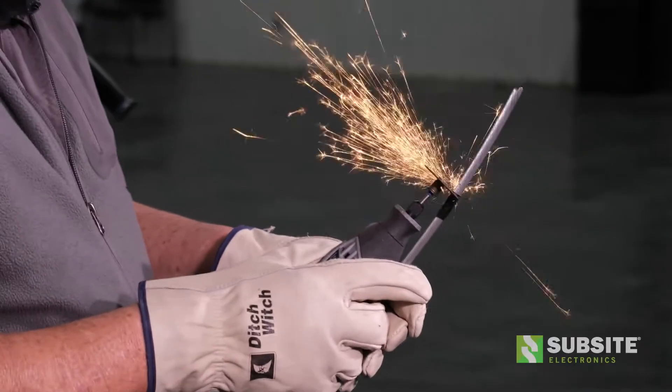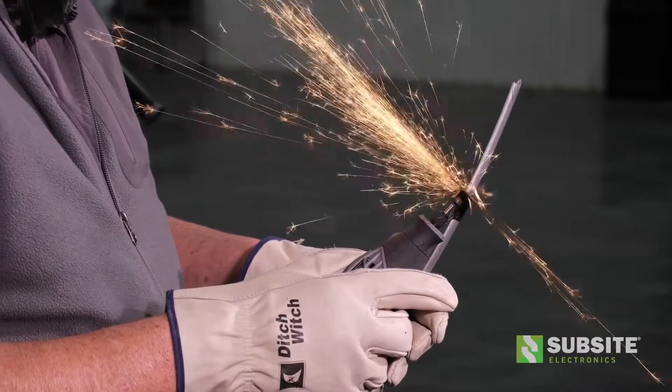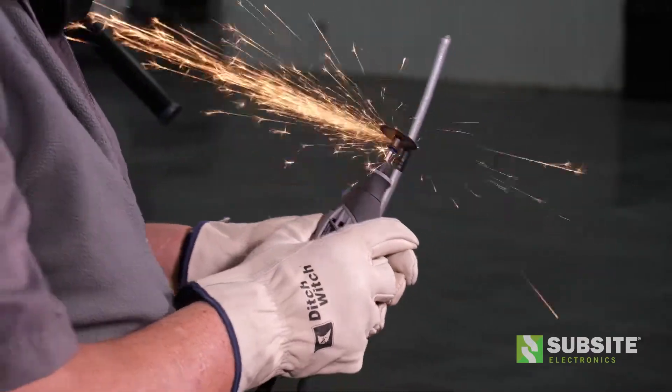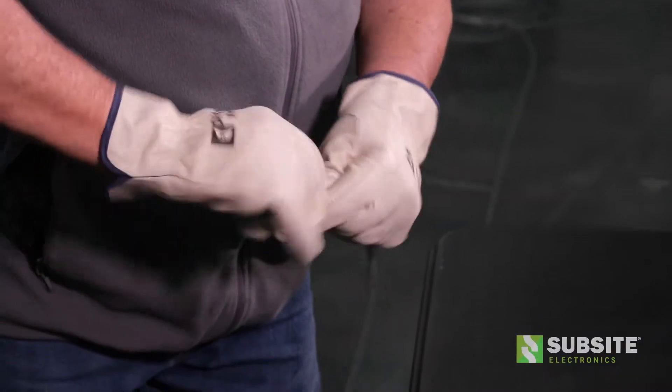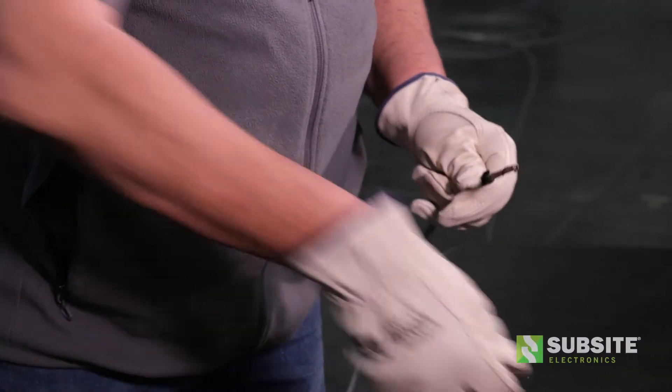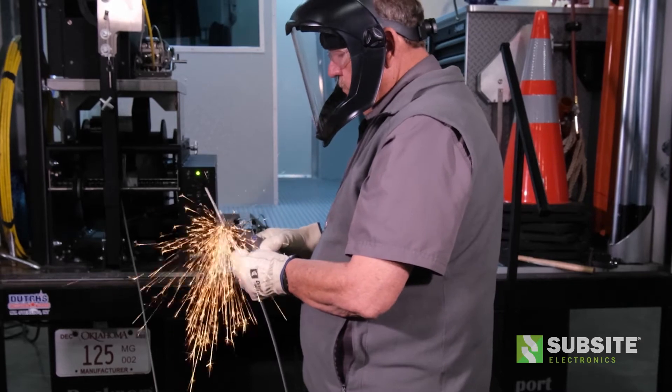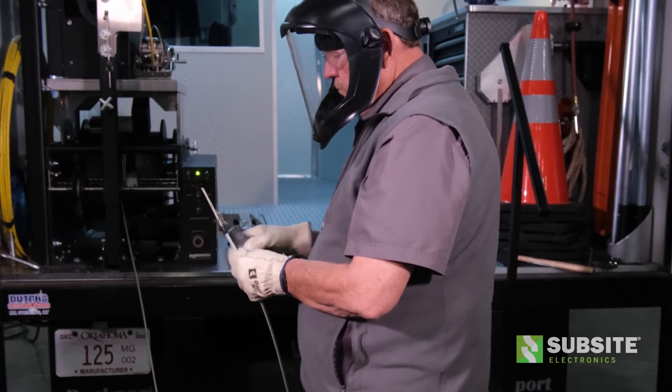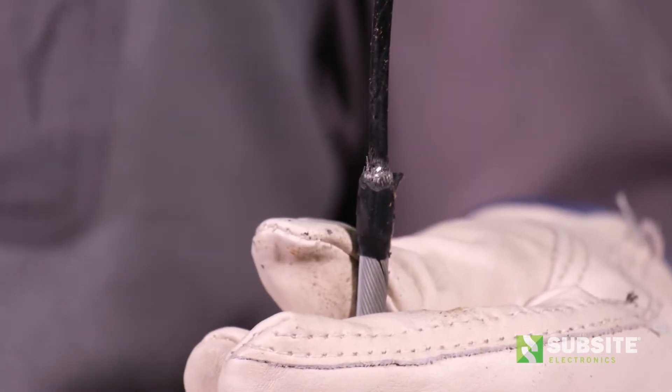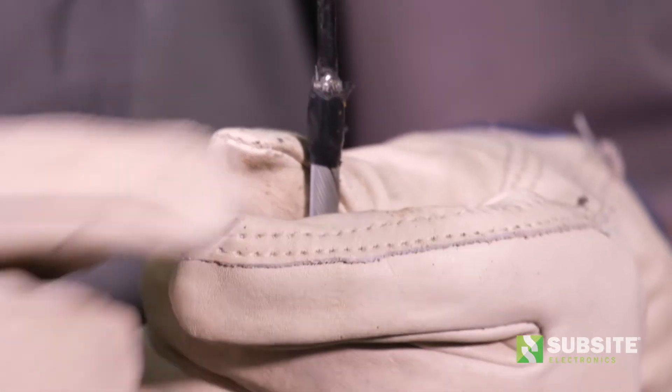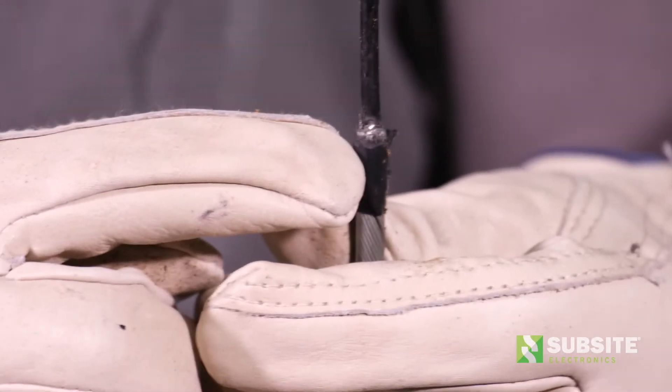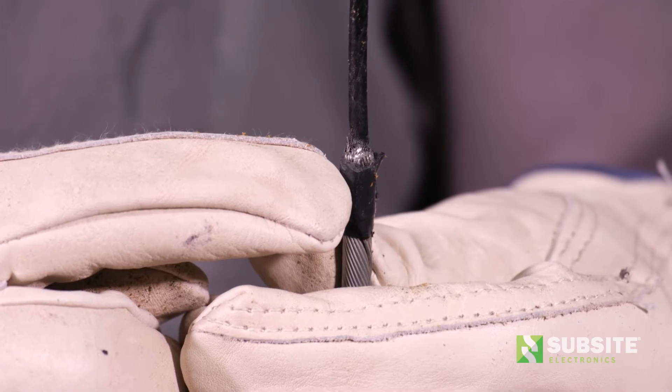To remove the outer braid, score the cable with a Dremel tool while walking around the cable and using the tape as a guide. Once scoring is complete, remove the outer braid as shown. Repeat the same process to score and remove the inner braid. Once the inner braid is removed, check to ensure that you've created a taper. If not, carefully taper the cable without damaging the black jacket.